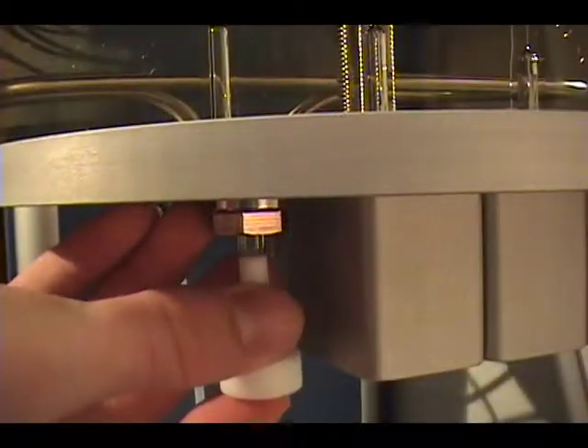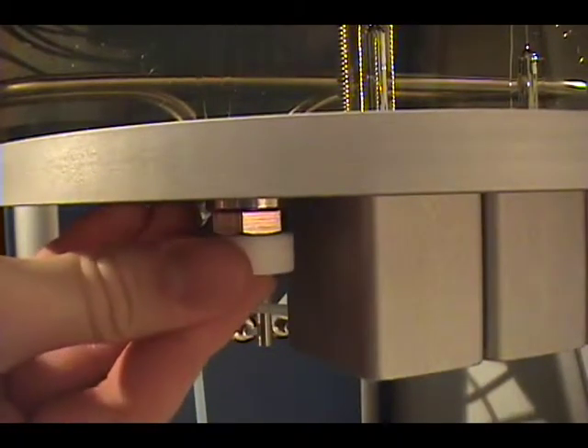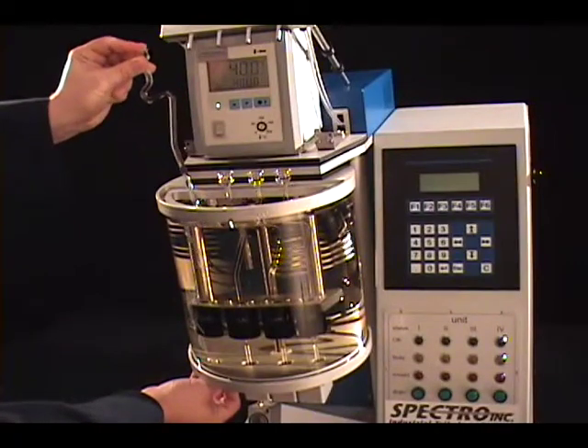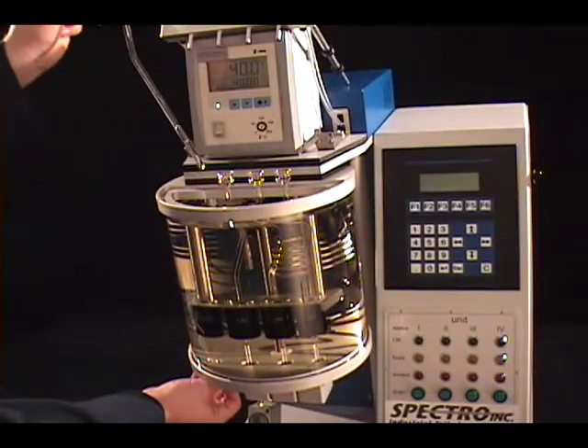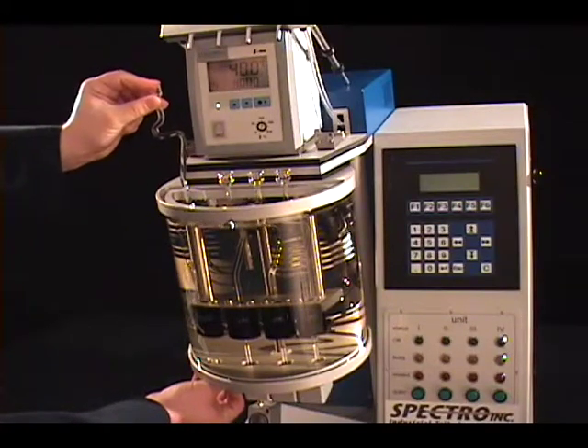Another advantage of the SpectroVisc is the ease with which a tube can be replaced. Unlike other viscometers on the market, a tube can be changed by anyone in a matter of minutes without the need to drain the bath fluid. As you can see, the sensor is not attached to the tube, making realignment of the sensors unnecessary.